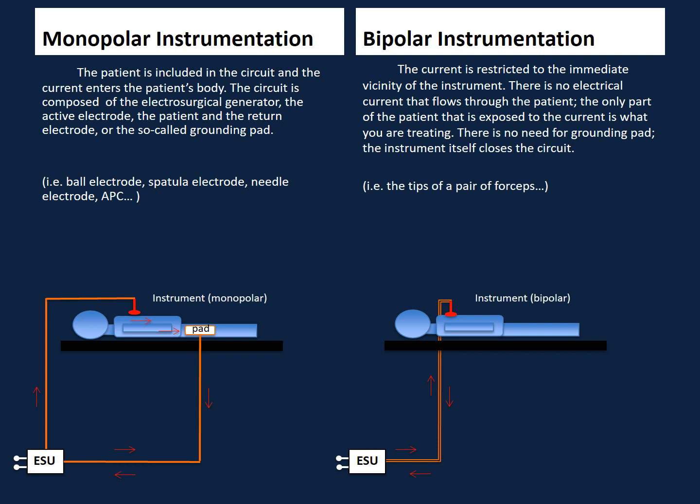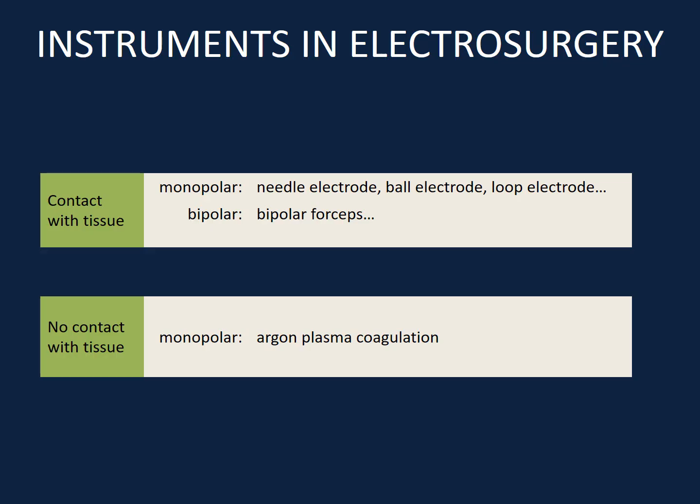Even with the new ESU, we continue to hear the expression "grounding the patient." Actually, we have moved from the ground reference to isolated units. In endoscopy, the active electrode is able to work either in a contact or a non-contact manner. In contact mode, the current is immediately dispersed into the tissue, whereas in non-contact mode, an arc is created between the electrode and the tissue surface, causing thermal effect.